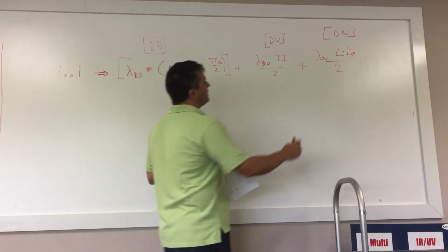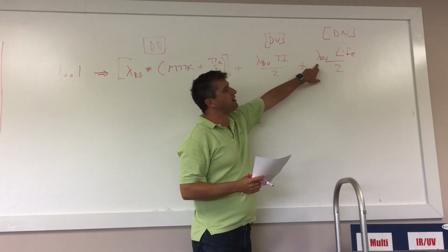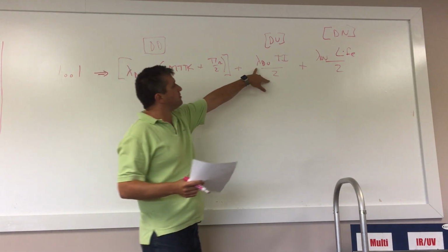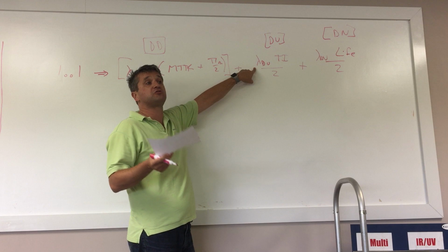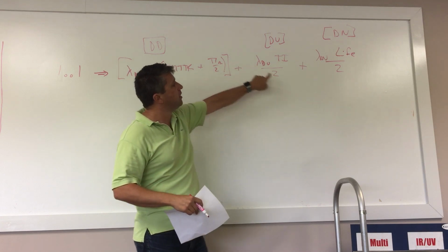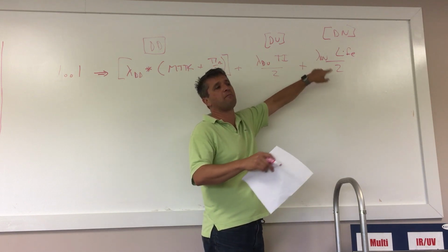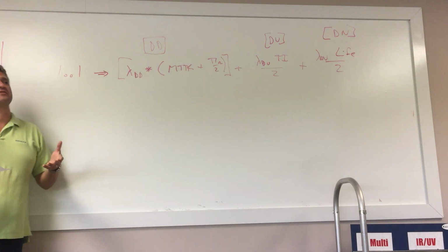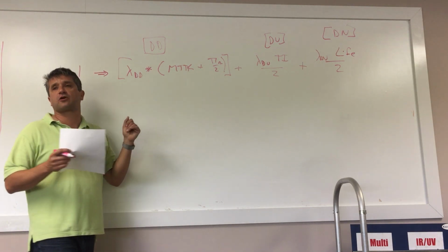The difference here is, put the D in there, DN. The failure rate is the rate of those failures which are never detected. So this lambda DU, we expect this portion of the dangerous undetected failures to be detected when you do your offline manual proof test. But this portion of failures will never be detected no matter how often you test it, because the testing processes are incapable of detecting that type of failure has occurred.